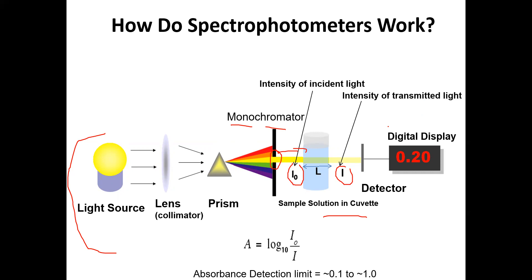The higher the concentration of your sample, the higher the absorption reading. This machine uses the logarithmic Beer-Lambert formula, comparing I versus I0. If there is no absorption, I and I0 will be the same and absorbance will be close to zero. If I is smaller than I0, you have absorption.